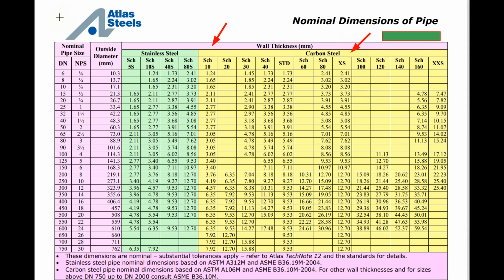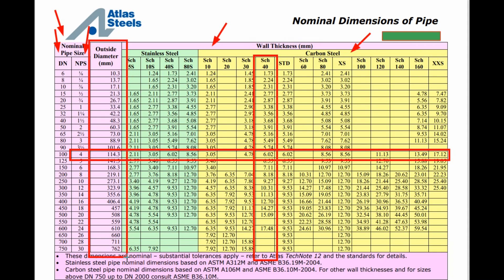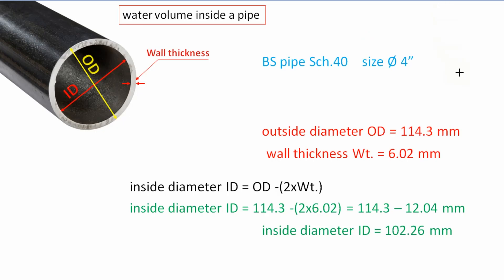The first two columns are for pipe size — the first column uses the DN system in millimeters and the second column uses the NPS system in inches. Our pipe size is 4 inch, so we select the row for 4 inch. We select the column for schedule 40 and also the outside diameter column. For a 4 inch schedule 40 carbon steel pipe, the wall thickness is 6.02 mm and the outside diameter is 114.3 mm. Using the formula, we calculate the pipe inside diameter equal to 102.26 mm.